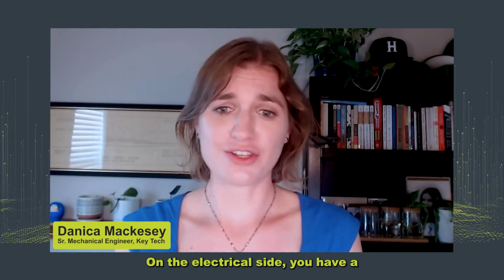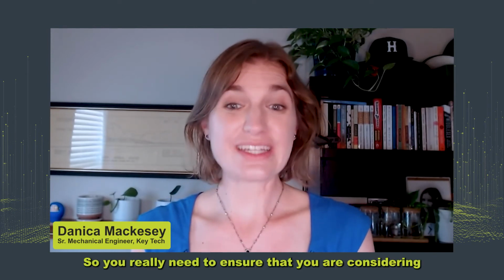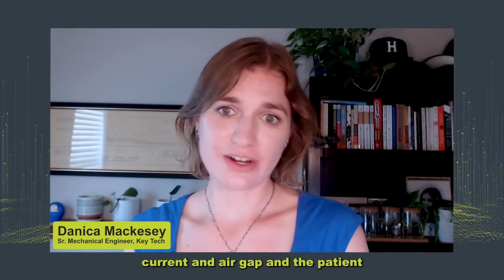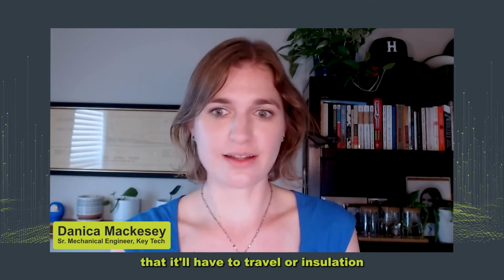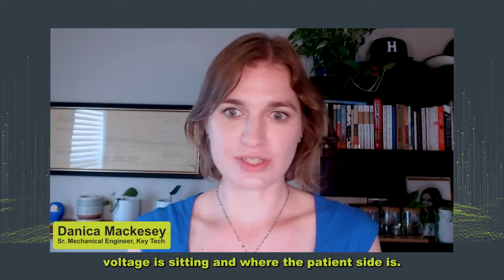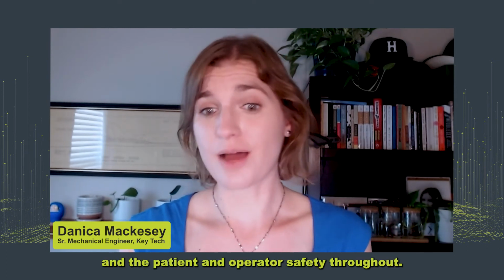On the electrical side, you have a pretty high voltage system that's potentially going to be in direct contact with somebody who is not able to say ouch. So you really need to ensure that you are considering what 60601 asks for, which is two different means of patient protection. Do you have enough distance between that current and the patient, an air gap, if that's feasible? If not, do you have creepage, which is the distance it'll have to travel, or insulation, or earth ground? We'll create insulation diagrams that show all of the stack ups between where that voltage is sitting and where the patient side is. That's something we can present along with the testing to show that we've really considered 60601 and patient and operator safety throughout.